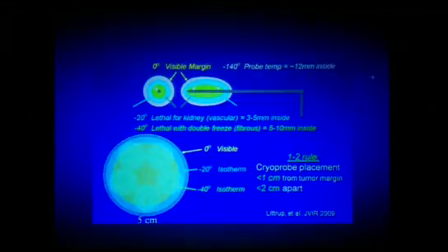The probe is usually a 17-gauge needle, which is placed in the actual organ, usually renal or liver. You can get minus 20 or minus 40 degrees, depending upon the organ that you're ablating, whether it's vascular or fibrous. You can use multiple probes.